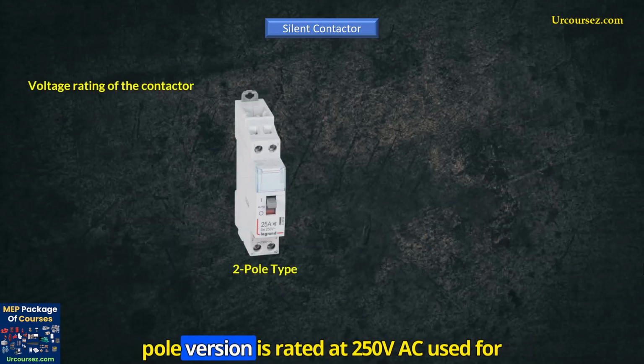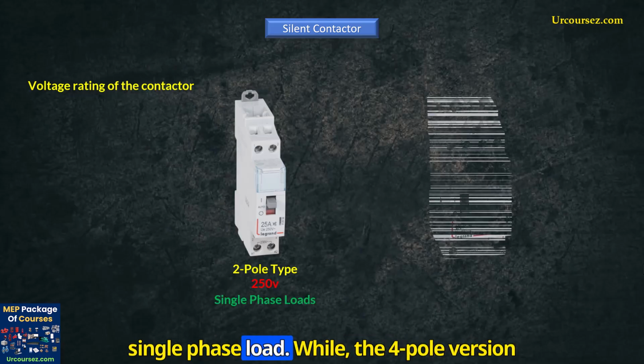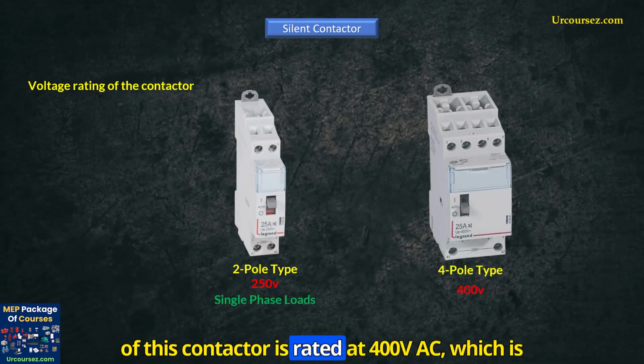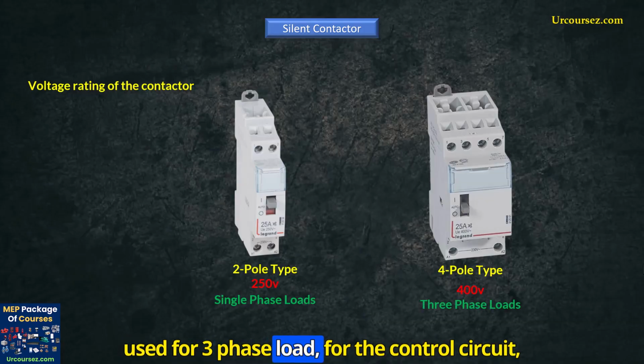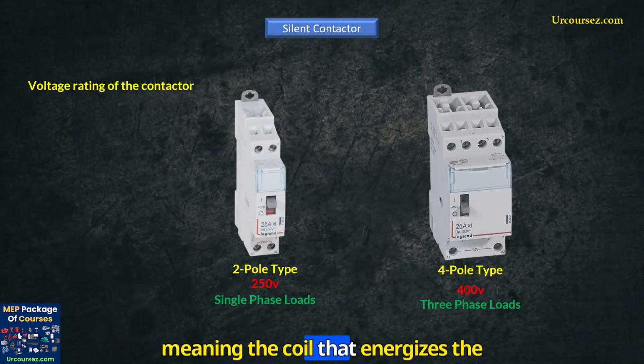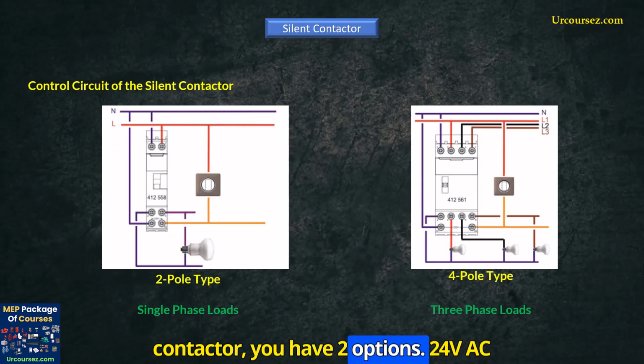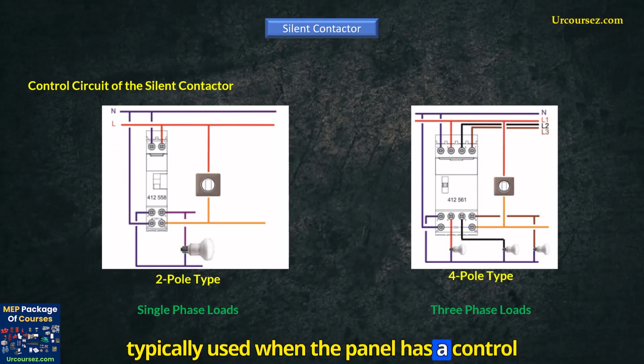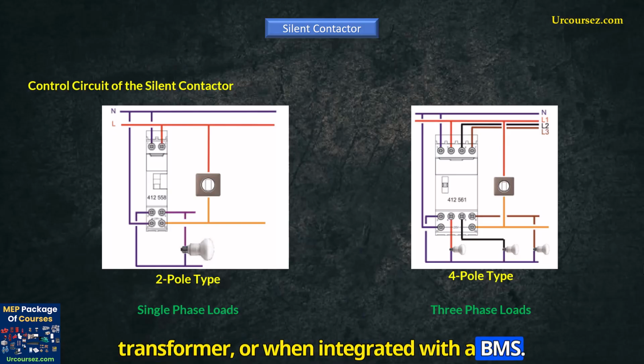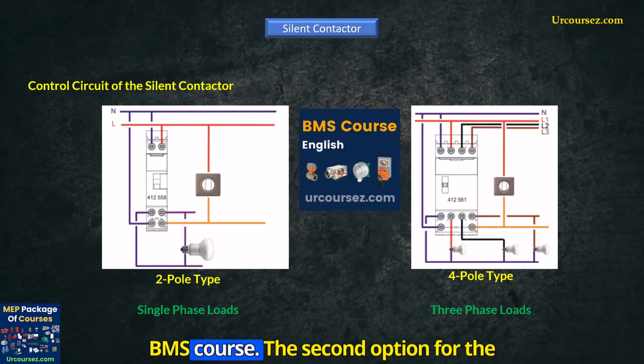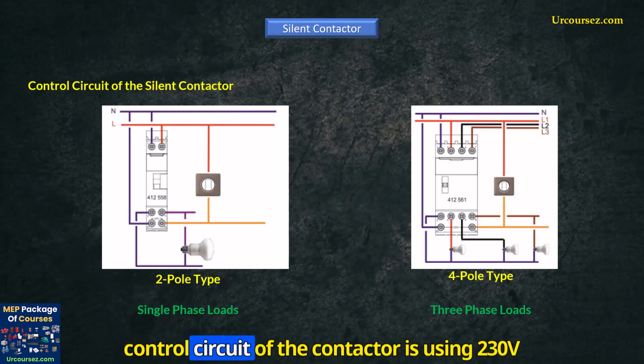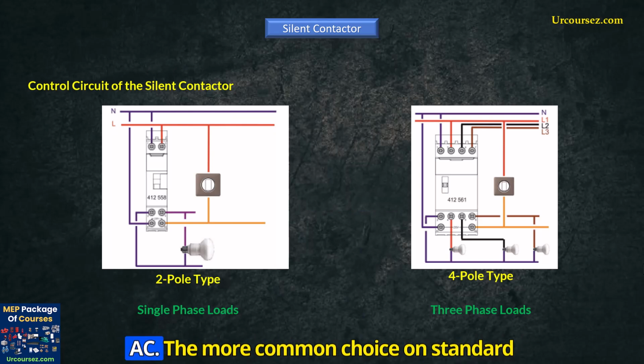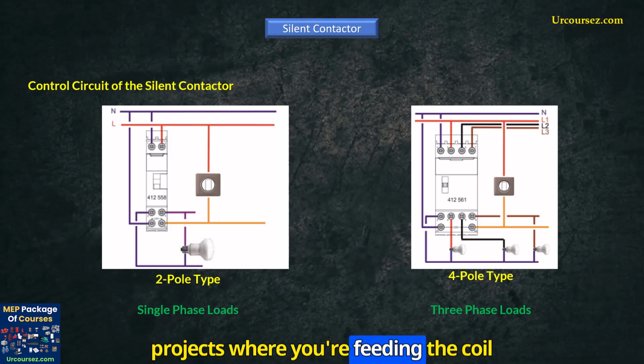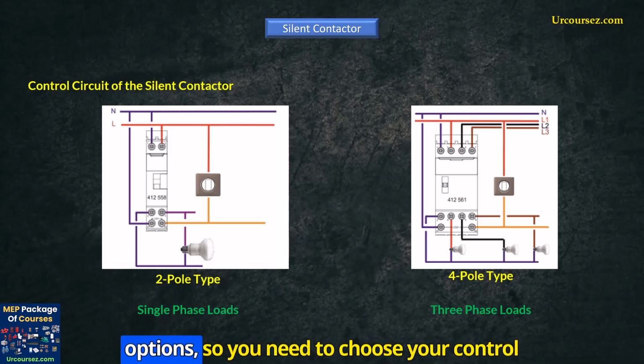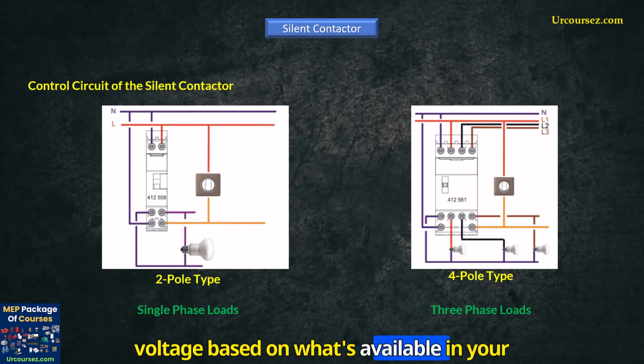Now let us discuss the voltage rating for the power circuit. The 2-pole version is rated at 250 volts AC, used for single-phase loads, while the 4-pole version of this contactor is rated at 400 volts AC, which is used for 3-phase loads. For the control circuit, meaning the coil that energizes the contactor, you have two options: 24 volts AC, typically used when the panel has a control transformer, or when integrated with a BMS. By the way, don't forget to have a look at our BMS course. The second option for the control circuit is 230 volts AC, the more common choice on standard projects where you're feeding the coil directly from a phase. From these two options, you need to choose your control voltage based on what's available in your panel design.